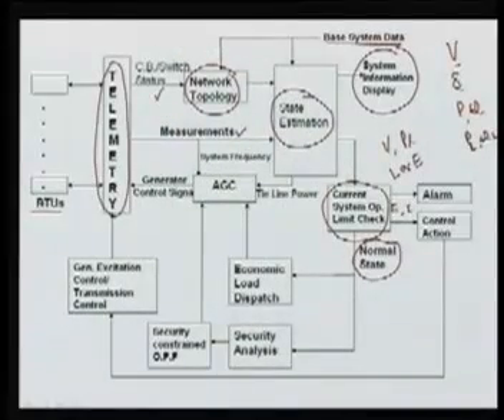So if it is a normal state, then we have to do other functions. If it is not in the normal state, then we have to give some alarm signal as well, so that the operators can be attentive and take corrective or preventive measures. At the same time, control actions can be applied at the various points required to move the system into the normal state of the power system.